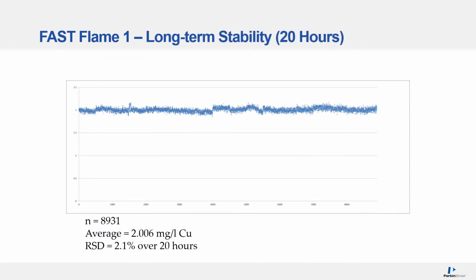And if 2 hours isn't enough to convince you, here's a longer term stability run. Same type of solution. It was a 2 milligram per liter copper solution, but we ran it over 20 hours. So in this test, we actually analyzed 8,931 replicates, and the RSD was only 2.1% over those 20 hours. So again, great stability.